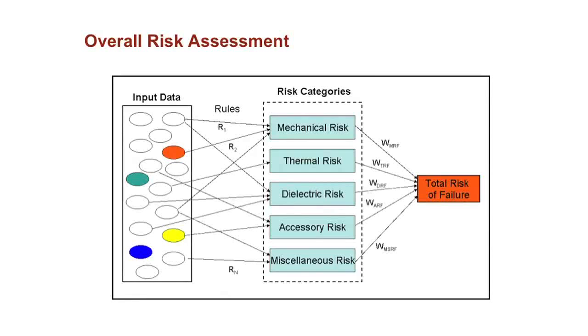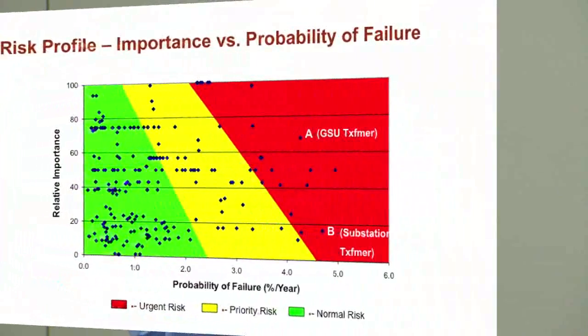Now the idea here is that, say, let's look at this one, you have a transformer that has a high risk of failure, but it's not that important, meaning it has a double. There's two of them together, so if one fails, the other one right beside it can handle the whole load. Or maybe if it fails, it's very easy to divert load, something like that. Versus one that maybe has a lower risk of failure, but if it fails, it's so disruptive to the system or to the customer that it needs to have a much higher reliability than another transformer. So that's important when you're comparing two transformers.